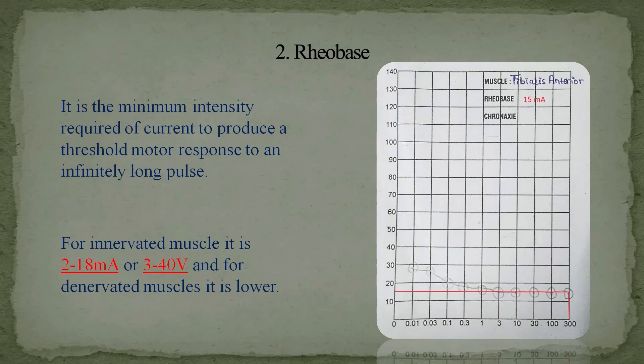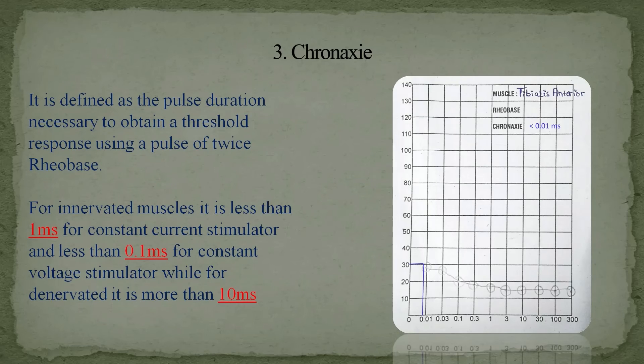Rheobase is the minimum intensity of current required to produce a threshold motor response at an infinitely long pulse duration. For innervated muscle it is between 2–18 mA or 3–40 volts; for denervated muscle it is lower than normal. In this case, rheobase is 15 mA at 300 ms pulse duration. Chronaxie is the pulse duration necessary to obtain a threshold response using twice the rheobase intensity. For innervated muscle it is less than 1 ms (constant current) or less than 0.1 ms (constant voltage); for denervated muscle it is more than 10 ms. In this case, chronaxie at 30 mA is less than 0.01 ms pulse duration.